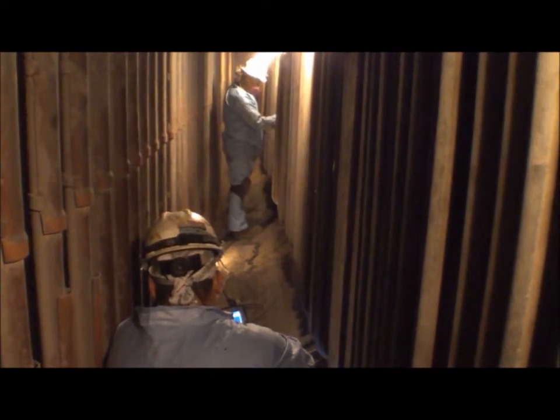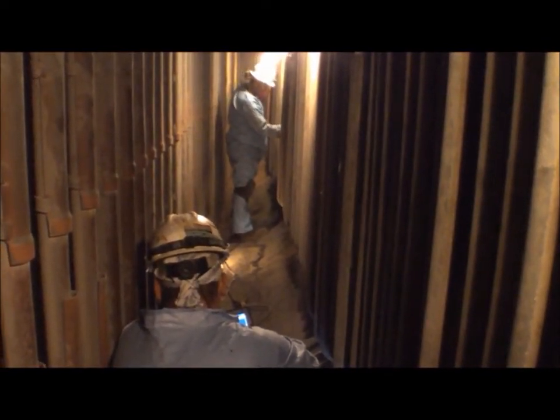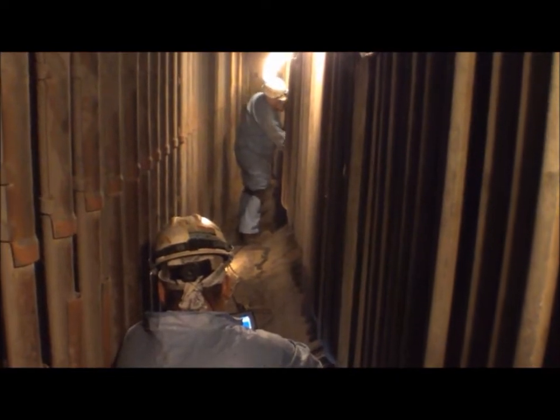If there is a magnetite indication observed, the tube is scanned again and the location of the deposit is marked on the tube and recorded.